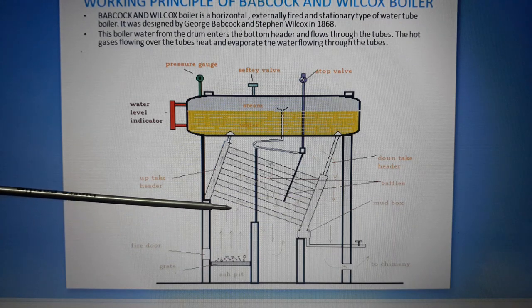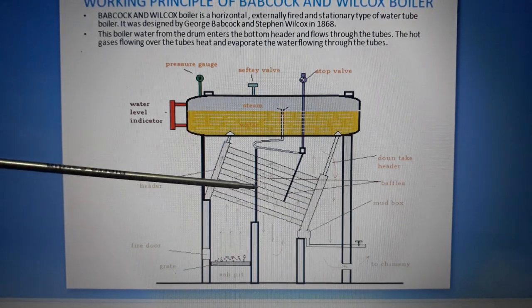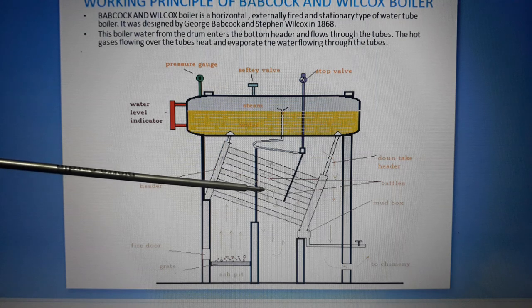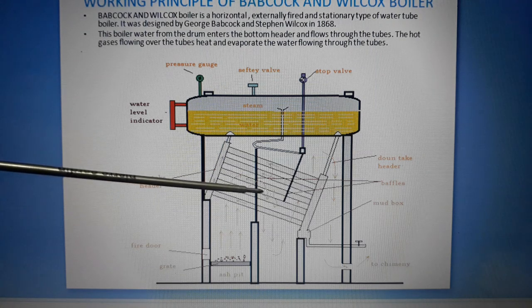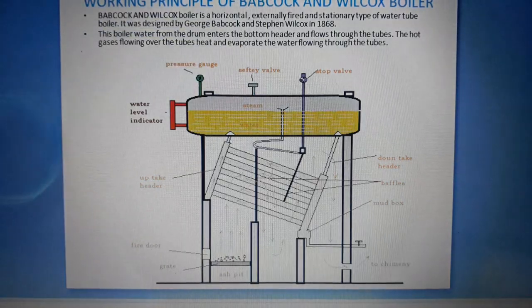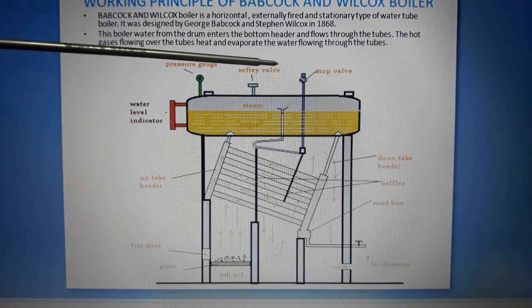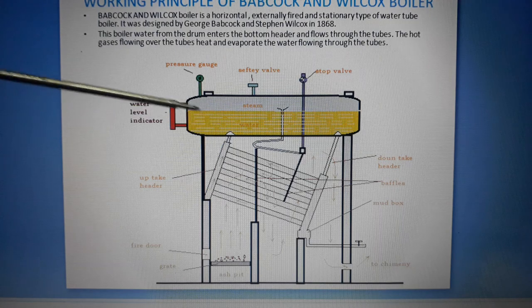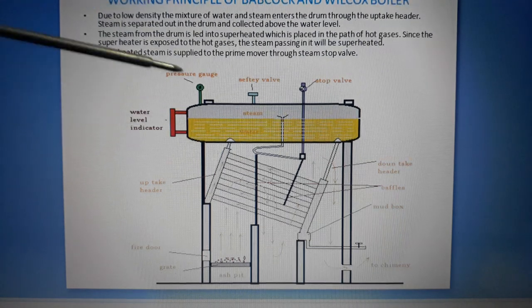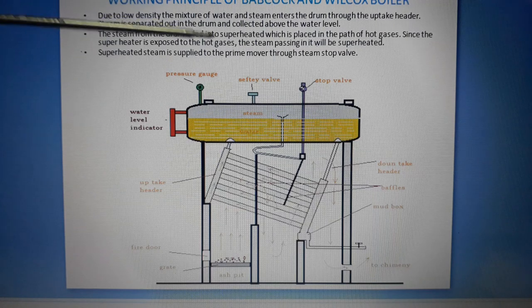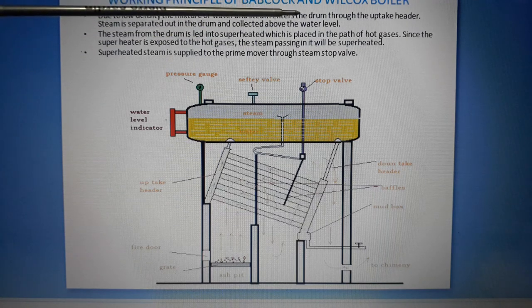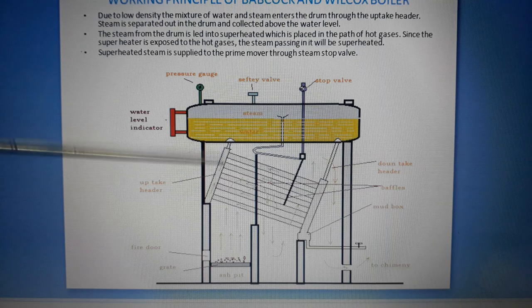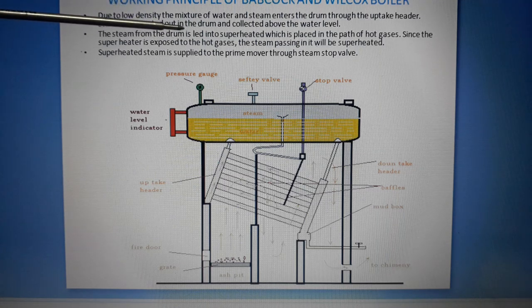When the hot gases flow over the tubes, heat exchange takes place. Whatever water flows through the tubes, heat is transferred and the water evaporates, converting into steam. Due to the low density of the steam-water mixture, it enters the drum through the uptake header. Steam is then separated out in the drum.